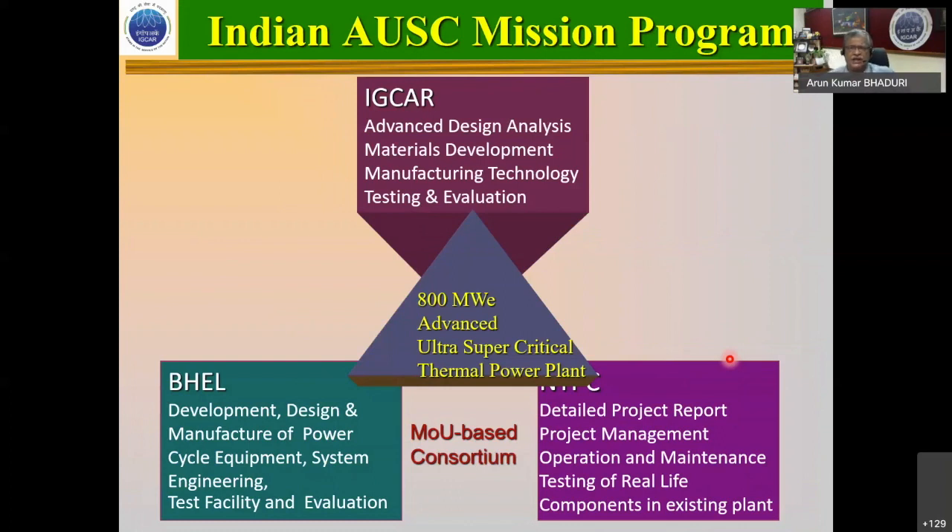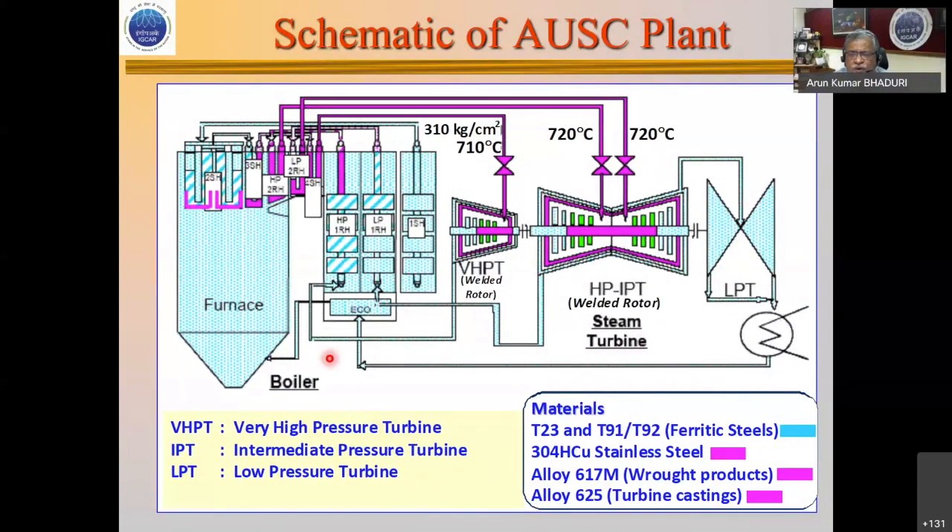Switching to the Indian Advanced Ultra-Super Critical (AUSC) mission program: we have an MOU between IGCAR, BHEL, and NTPC for materials development, manufacturing technology, testing and evaluation, ultimately towards an 800 megawatt AUSC plant that will achieve substantial reduction in carbon emissions and efficiencies of about 48% versus 35–39% presently. We did not design the entire plant from scratch — only the high-temperature sections highlighted in pink were replaced. The three materials we worked with are 304HCu stainless steel, Alloy 617, and Alloy 625; all others are traditional materials.